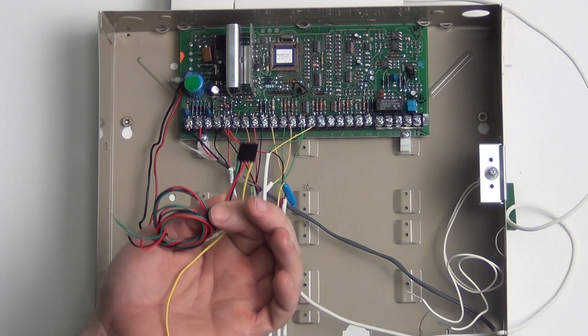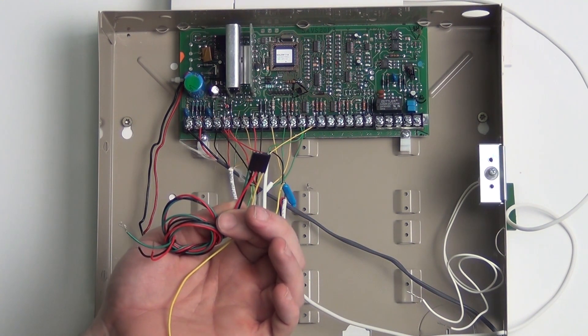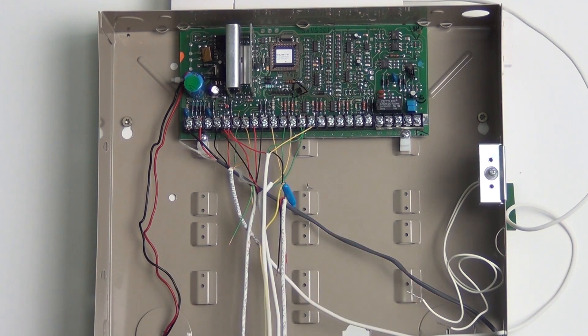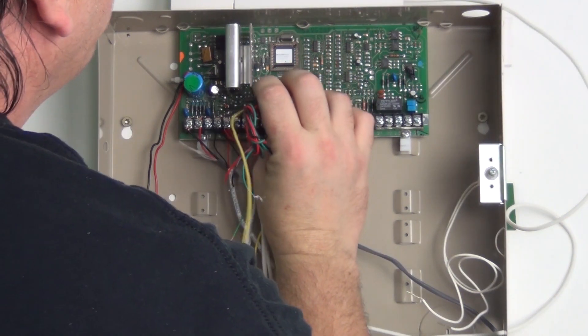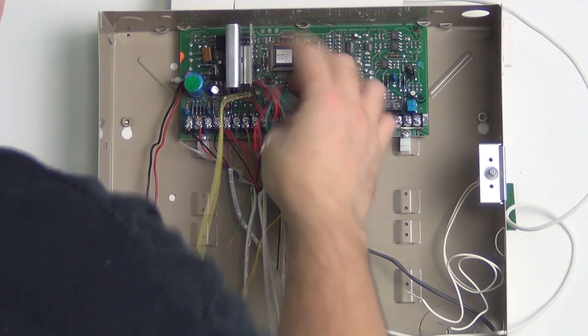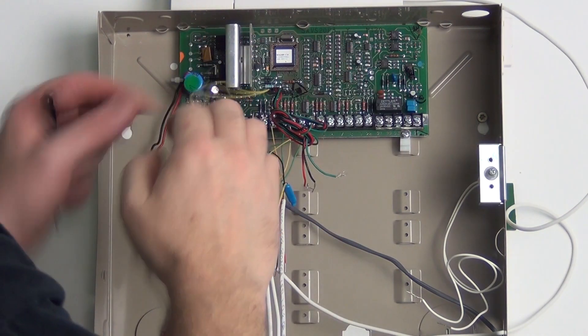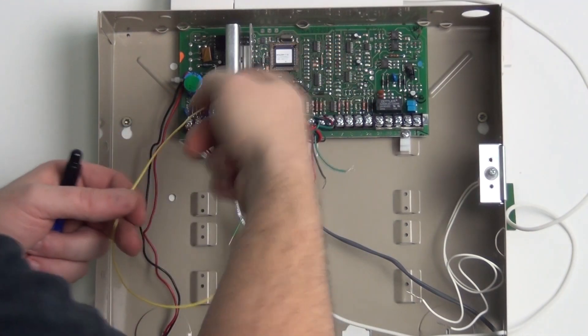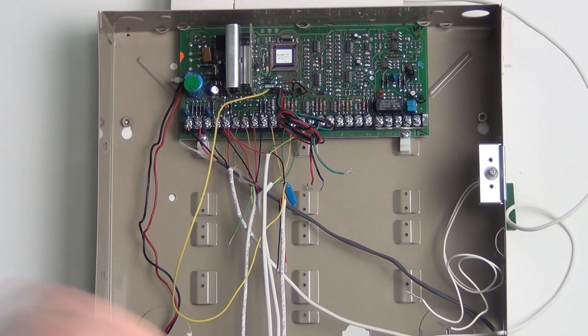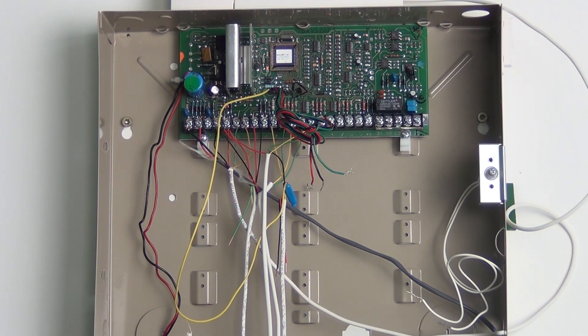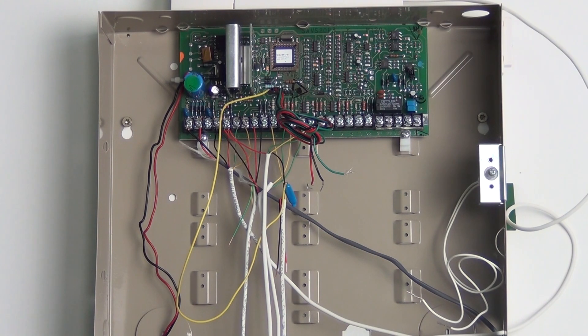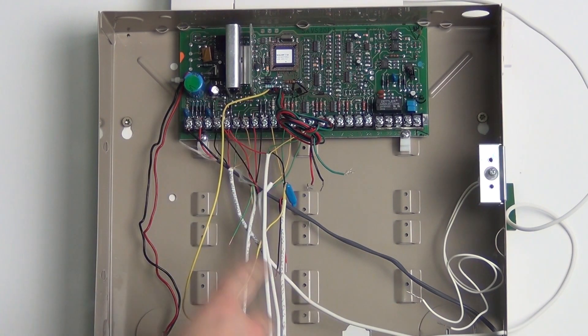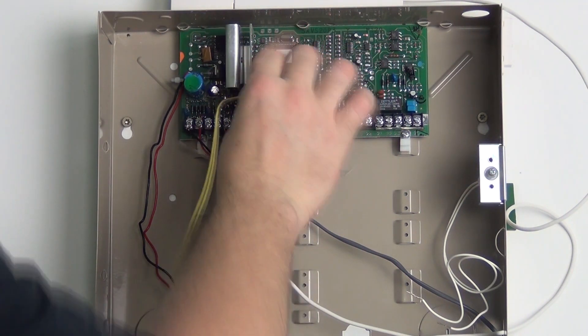What you will usually use is a TR4120 for your trigger pins. You are going to plug this in to the trigger pins on the Vista 20P, which are located right above the terminals to the right of the heat sink. Your negative wire is going to go to the first pin on this row, which is trigger pin 17. When you get a smoke alarm on this zone, because of this trigger pin wiring and the programming that you will do for it, it will drop power on your 4-wire smokes just long enough to reset them, then it will bring it back up. You will have to run your positive to terminal 5, and then your negative wires are all going to connect onto this wire for trigger pin 17.